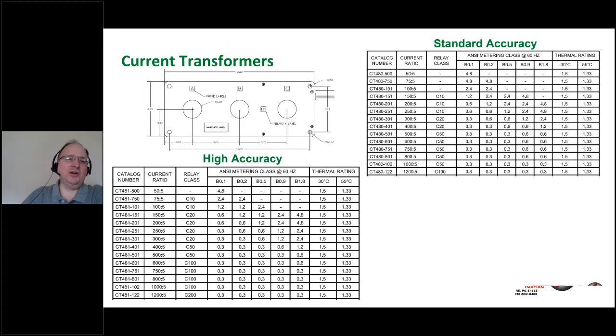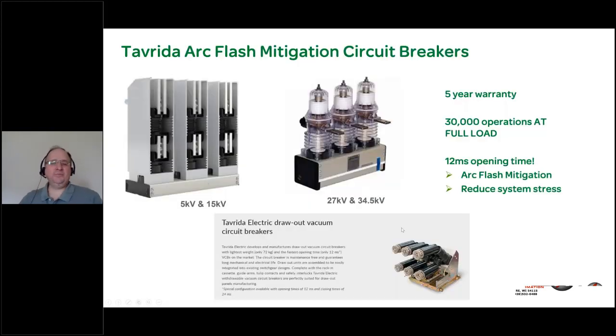We offer, of course, a wide range of current transformers, both standard and high accuracy, available in the design. This circuit breaker is, I'll be real up front here, my current favorite circuit breaker. We ourselves, L3, have no commercial connection to Tavrida. We're not representatives for Tavrida, but we are huge proselytizers of electrical safety, maintainability, and reliability. And this Tavrida circuit breaker has been taking the market by storm because it is a game changer. The breaker comes with a 5-year warranty, and it is rated for 30,000 operations at full load, which is incredible.